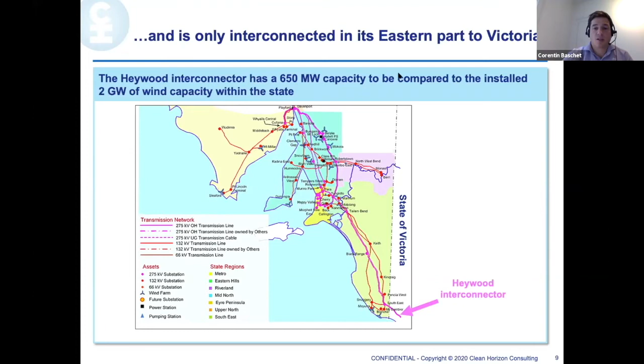Looking at what happened in past years - not fresh news, but I think it's good to take a step back and analyze, because it's easier to see and find out why and how things happened. Back in 2016 and 2017, there were actually 4 blackouts in South Australia. In September, huge storms damaged transmission lines, and the wind ride-through settings were not compliant, so the voltage drop caused the generation to trip.